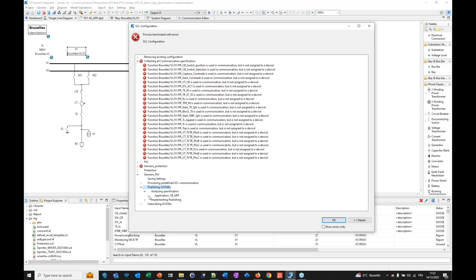But if I show you the result, for example for the Siemens PIU, we publish some GOOSE. If I go a little bit down in this dialog, you will see we have the CB application, which extends some GOOSE from the Siemens PIU. In this application, we will exchange the position of the breaker, for example, and to implement this, we have created a control block, the GCB F1. Inside it, we generated the data set in the SCD file, put the position in the data set, and prepared the subscription in the protection IED.